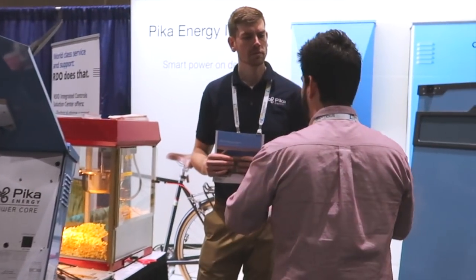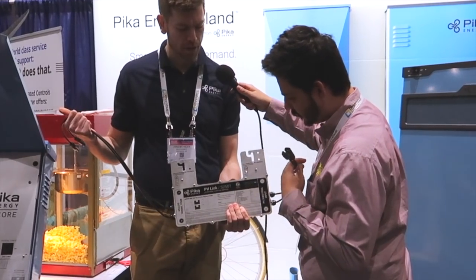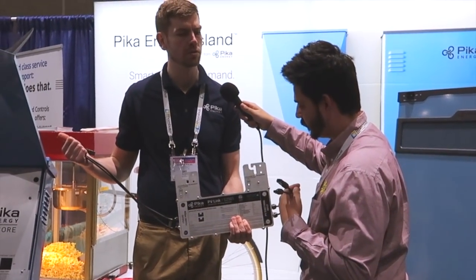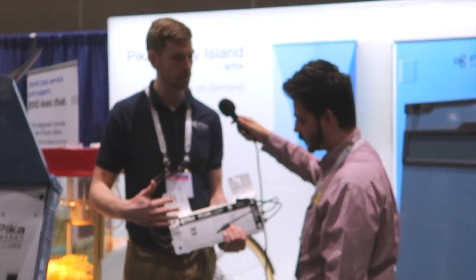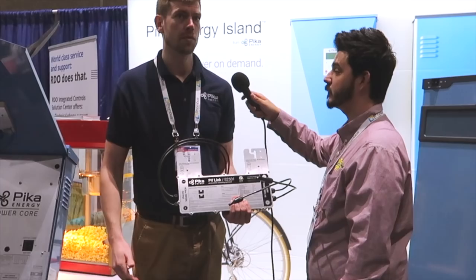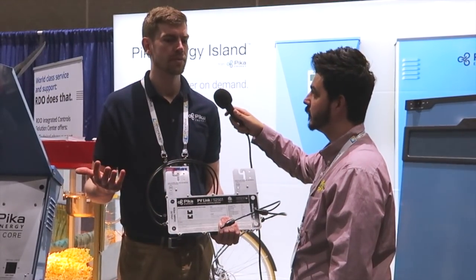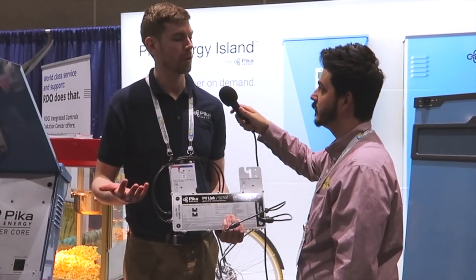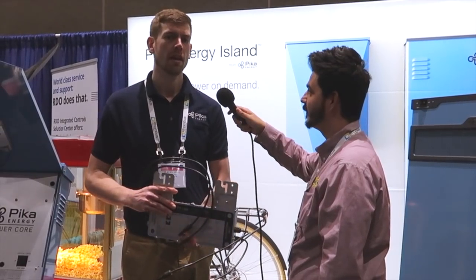A lot of it has to do with this big thing right here — the PV-Link. If you're familiar with microinverters or DC optimizers from Enphase or SolarEdge, this is doing the job that eight or nine of those module electronics are doing. This is a PV-Link optimizer — a substring optimizer — and it controls up to 420 volts of open-circuit input. With Panasonic HIT modules, that's eight modules. Not only will installers save time on the roof, they'll also reduce the hardware risk on the roof. Solar modules are incredibly stable and don't fail — what fails more frequently is the electronics that control them. So if you reduce that by a factor of eight or nine and put one beefy unit on your roof instead of 30-plus small electronic devices, you'll have a more stable, more robust system long-term.